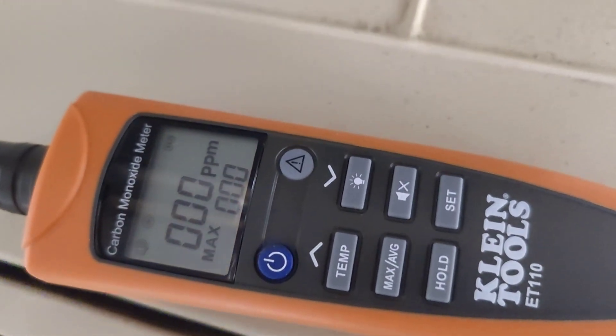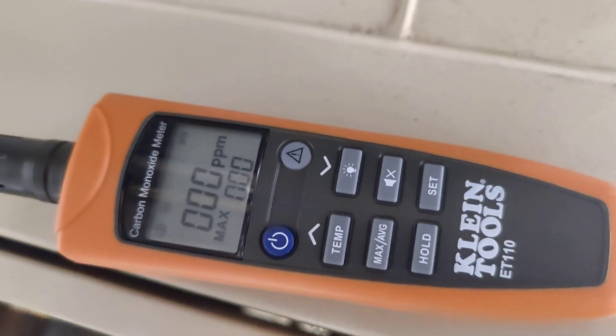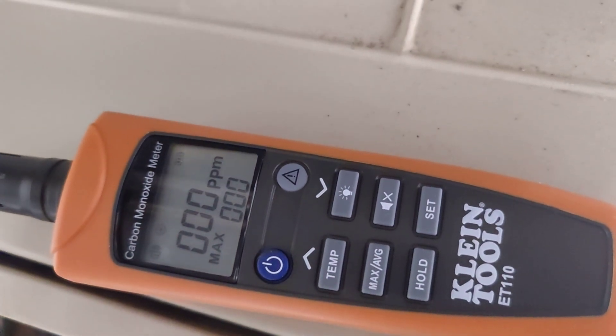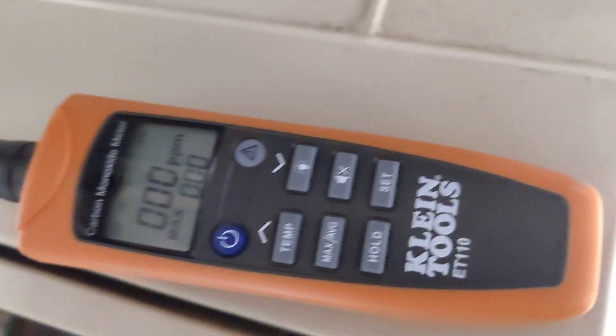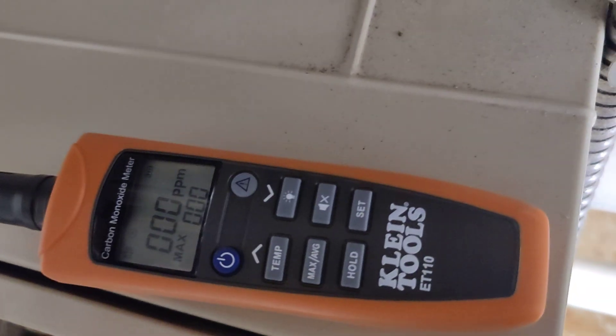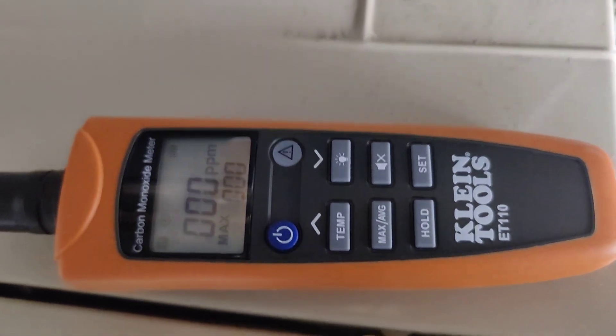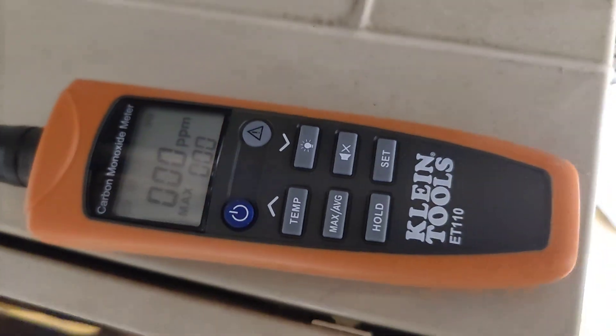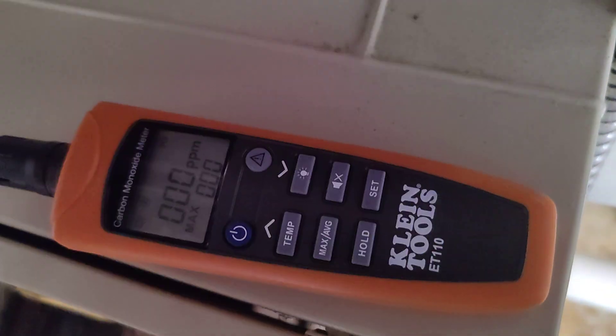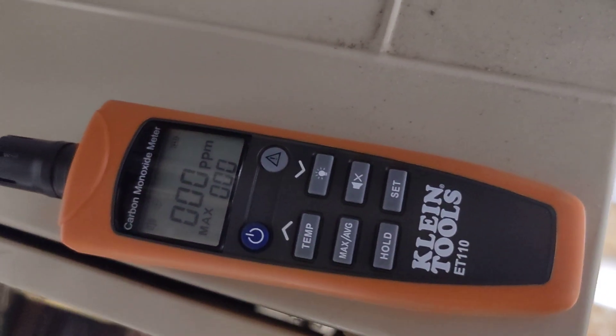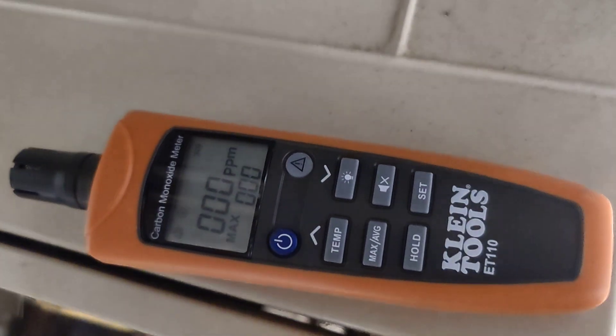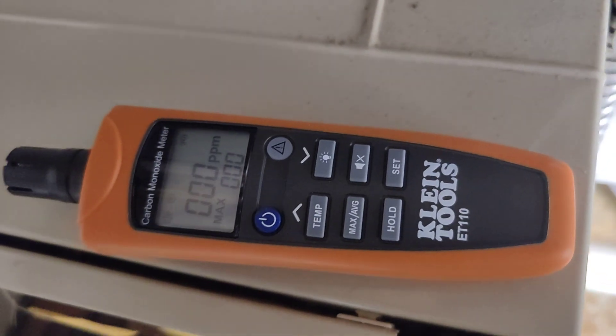So I'm not getting any carbon monoxide, which tells me right away I'm not getting any rollout of this heat exchanger.